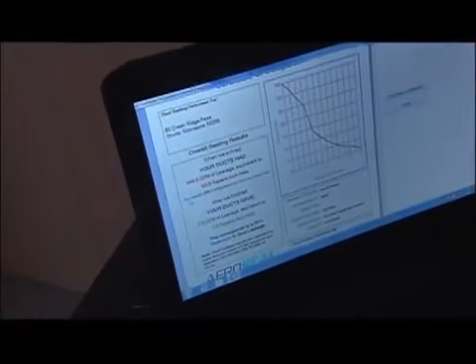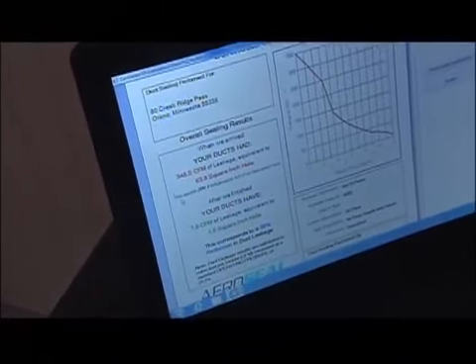Absolutely, you've really sealed up all those little holes. And by doing that, we're going to get more comfort in the home, and secondly, increase the quality of air in the home—I'm not going to be pulling all the poor, bad air out of the walls anymore. Last but not least is the energy savings. Typically, by having your duct system sealed, you can save anywhere from $250 to $800 a year by having this process done. Wow.